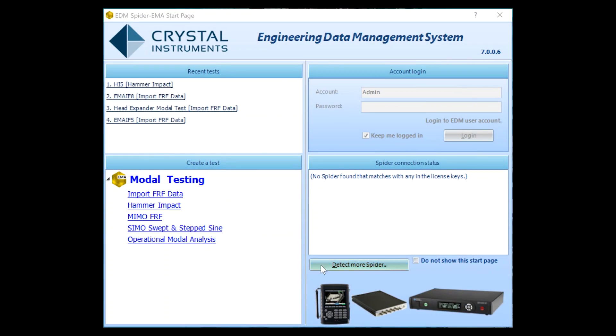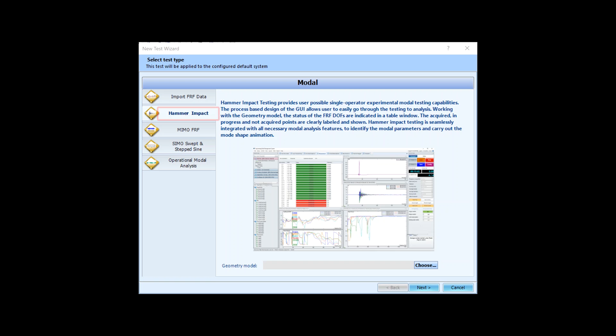To start the test setup, open the new test wizard. There are several test types listed here. These will determine how the modal data is obtained. We need to select hammer impact for this test.